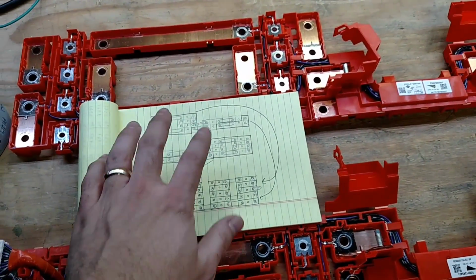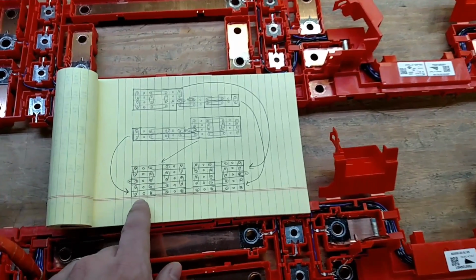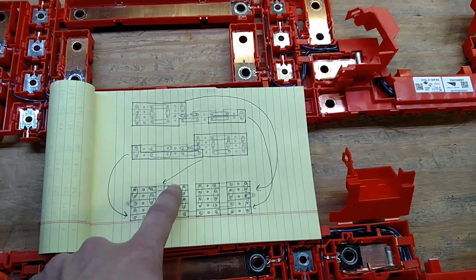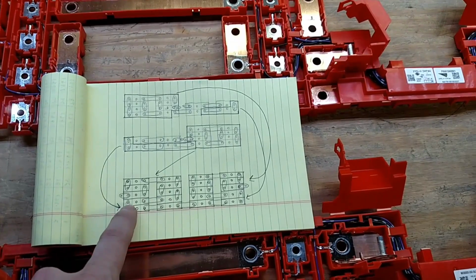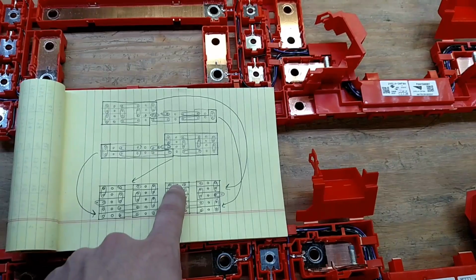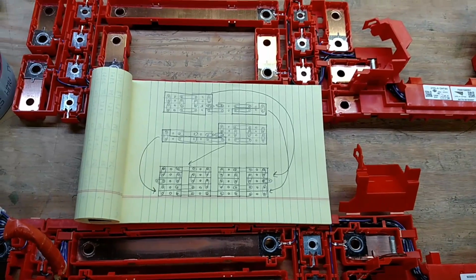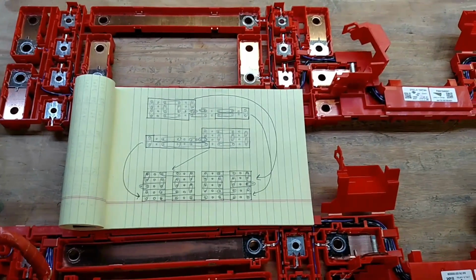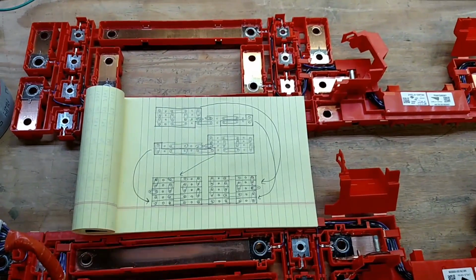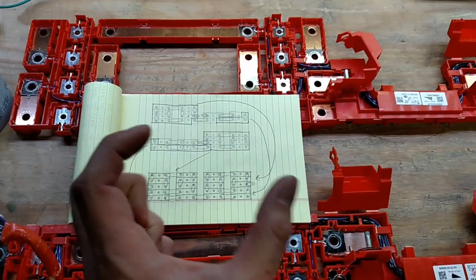So essentially, right now they have theirs in the correct order that it needs to be, and I'm going to have this be essentially module 48, 47, 46, 45, 44, 43, 42, 41, 40, 39, 38, 37, 36, 35, 34, 33, 32, 31, 29, 28. Then I'm going to skip the next 8 modules, and when we get on the other side, I'm only going to have 1 through 20 modules. So the BMS will have the middle 8 modules removed.